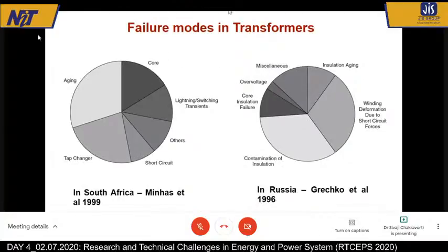Then if we look at the failure modes in transformers, if you look at the left-hand side diagram, it's a study in South Africa, where you can see the different failure modes. And you can see that the largest block of the pie chart is aging. And when you talk about aging, it is the insulation.